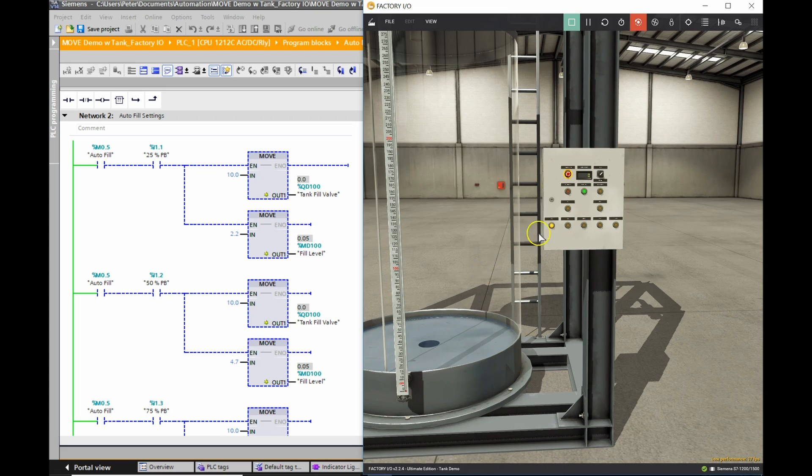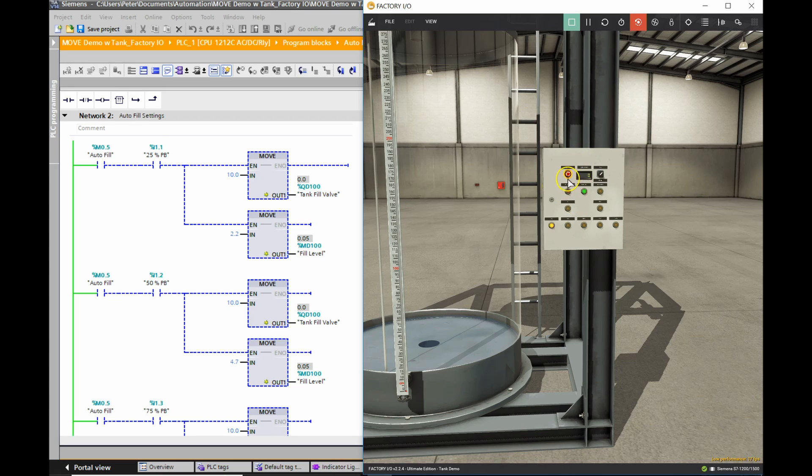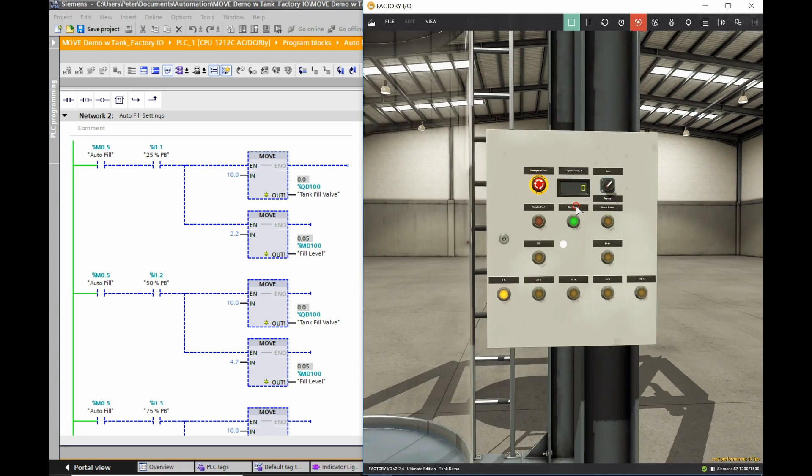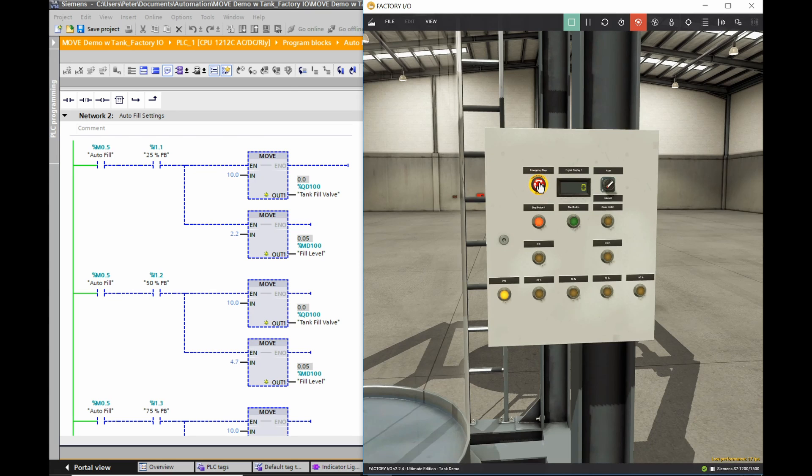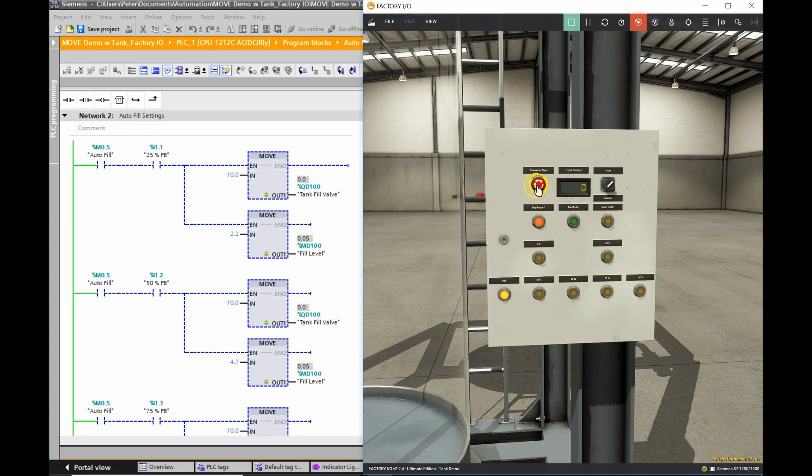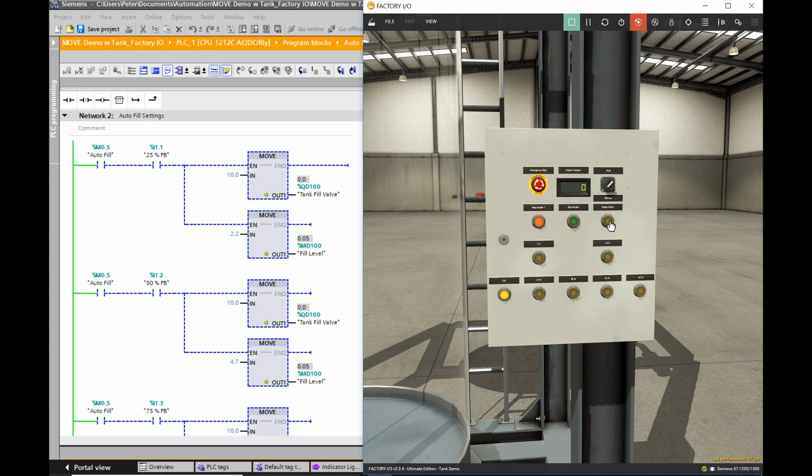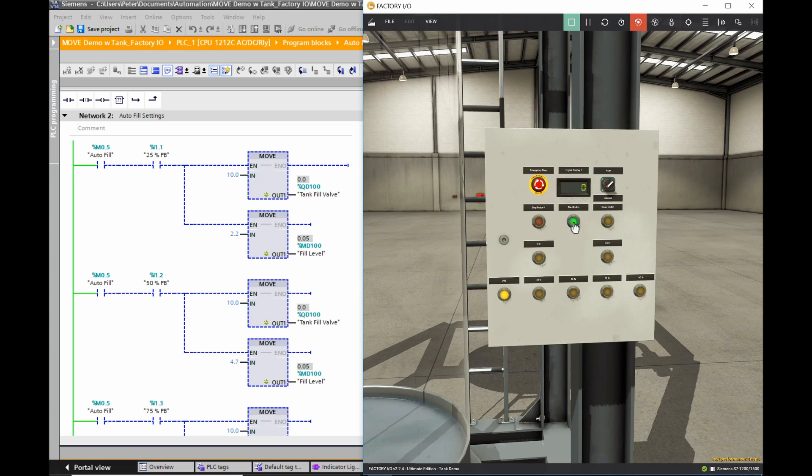The other thing that I have in my program is that say there was an emergency and we need to stop everything. Then we can hit the E stop here. When I hit the E stop, I have a flashing bit here now on my stop push button to tell me that not only have I stopped, but I'm in the E stop situation now. So I need to check on what's just happened. Then I need to revert the E stop back to its rest state. I need to reset my push buttons. So I have a reset program that runs for about four seconds. And once that finishes, I have a nice solid light here on my stop. So I know that I'm ready to go. And then I can hit my start push button and start everything up again.